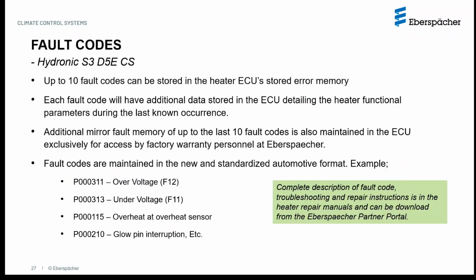Now, when it comes to the fault codes, yes, the newer generation, the memory capacity has increased. So we have up to 10 fault codes that can be stored in the storage memory. In the 1st generation, the heater could only store up to 5. So that's almost double the capacity. And also, in terms of the active codes, you could have 10 fault codes in the active fault memory in the newer generation heaters. Whereas in the older generation, you could only have 1 active code. Another important differentiation is that every code will have additional data. When I do a demo, I'll show you what that additional data looks like. This is only on the newer generation. It's not on the older generation. And in addition to all of this, the newer generation also has what's called as a mirror fault memory.